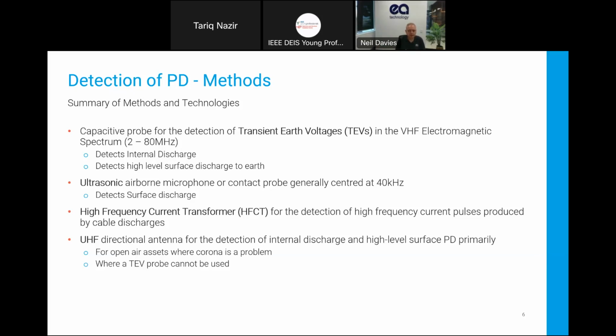You can use it for directionality of finding internal discharge and high level surface discharge, where the transient earth voltage, which is operating in the HF to the VHF range, will basically swamp a yard. There will be lots of signals everywhere, and you can use UHF techniques to basically localize where things are coming from. Also, where TEV probes cannot be used, where you cannot actually place the capacitive sensor on the outside, then UHF antennas are another way of using the electromagnetic technique from a distance. So they're the techniques.